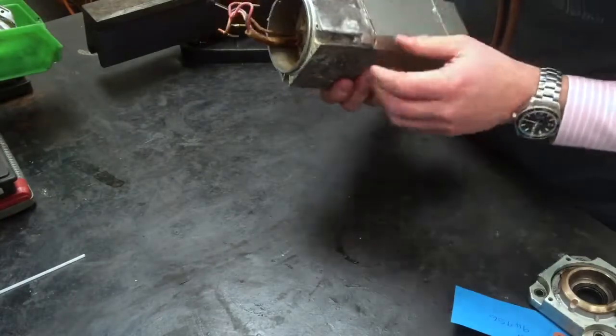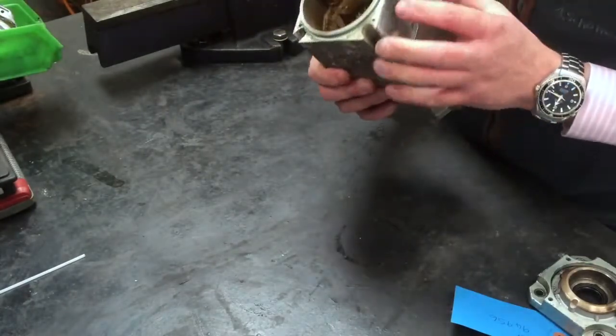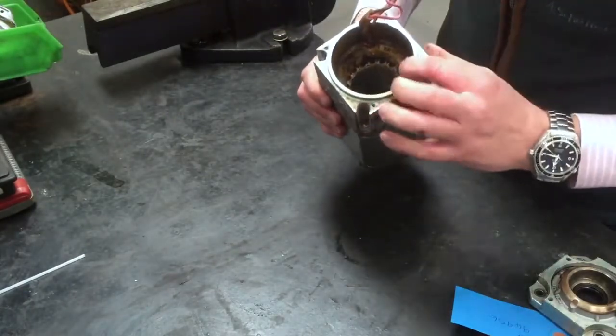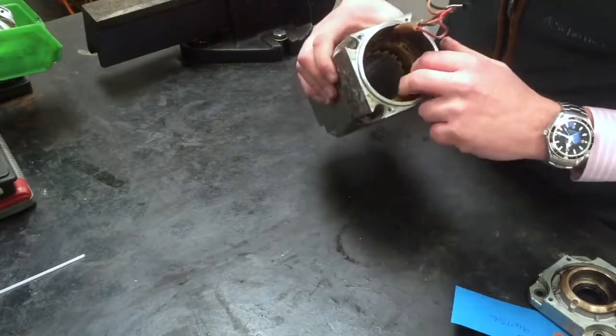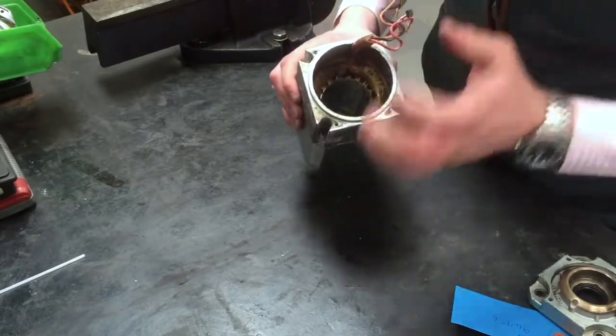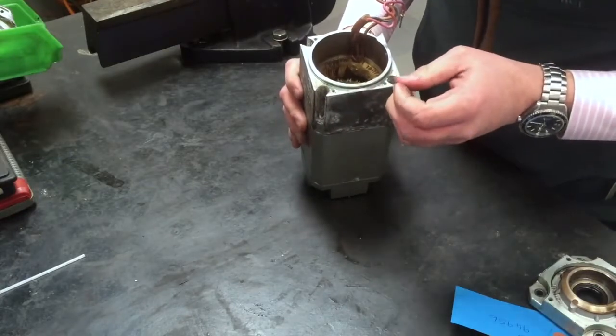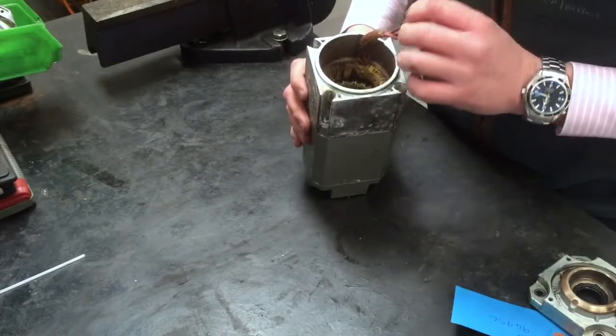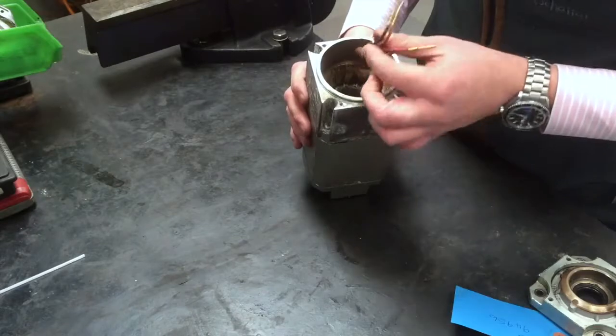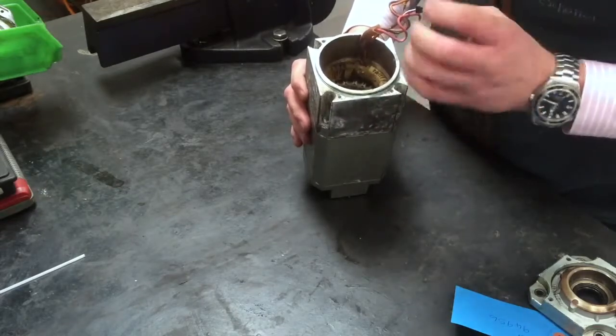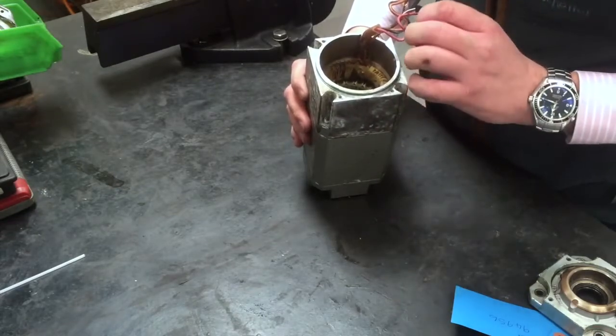Now the stator, we can see that there has been corrosion on the rear end for this stator. We will clean this up as well and also we have got the motor windings in there. We know we were okay with the insulation resistance to earth. But what we need to check too, we need to surge test this winding and also carry out the high potential test to make sure everything is fine with the windings itself.